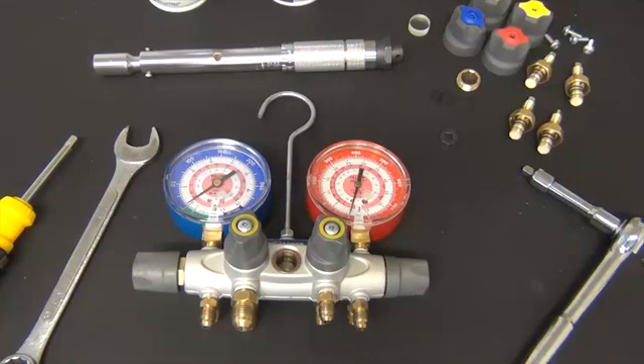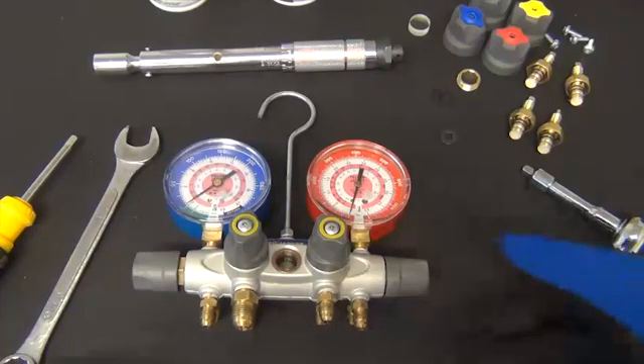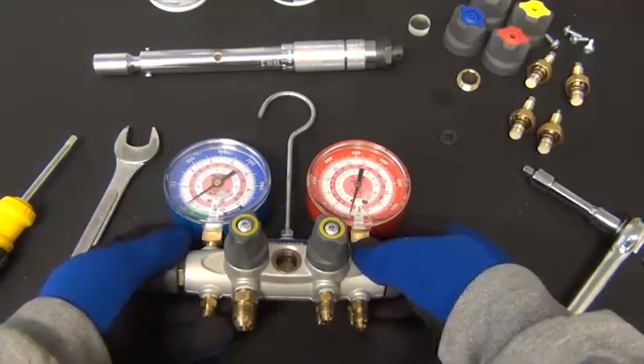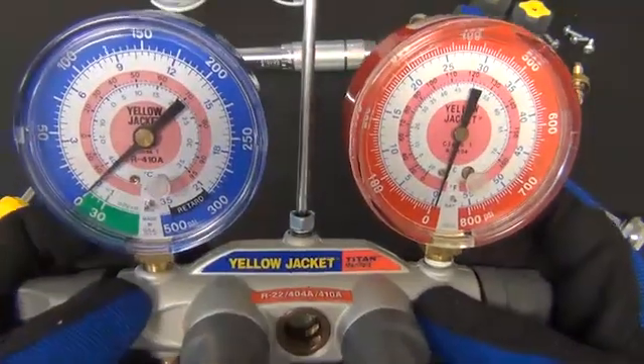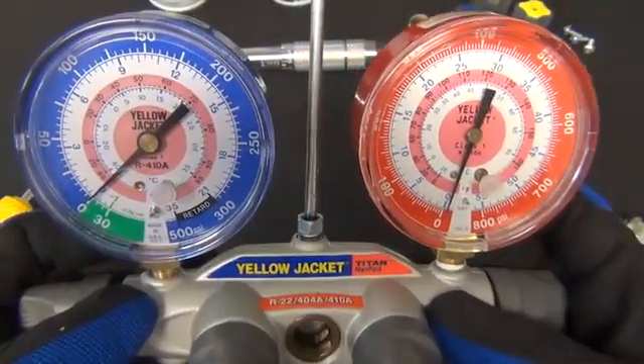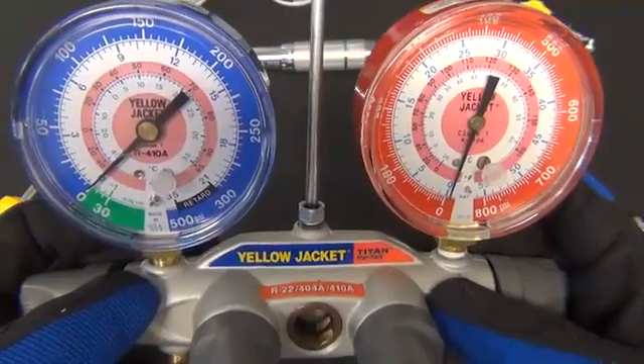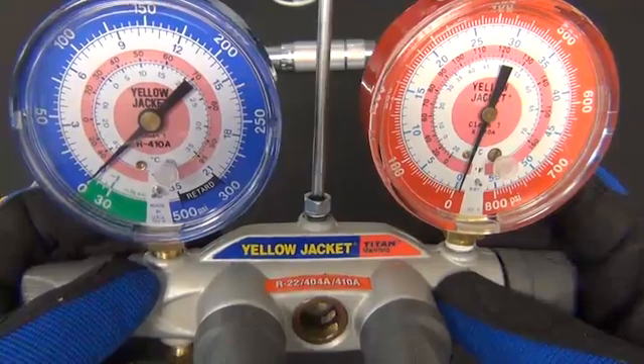When rebuilding any manifold it is very important to make sure there is no pressure or refrigerant left in the manifold. Your refrigeration manifold may contain refrigerant under pressure. Extreme caution should be observed when rebuilding any manifold. Wear safety glasses and gloves to prevent personal injury. First check gauges for any pressure readings. If there is any pressure on your gauges, safely release the pressure before proceeding.